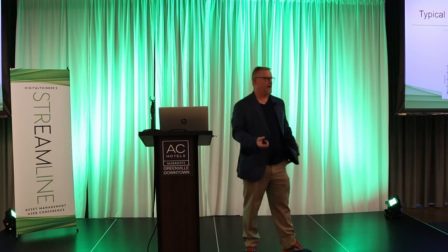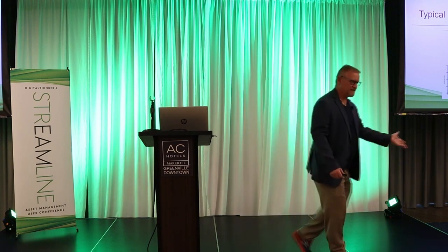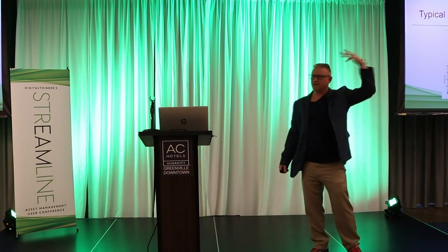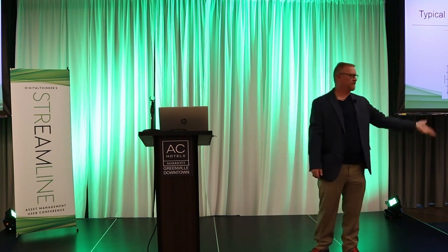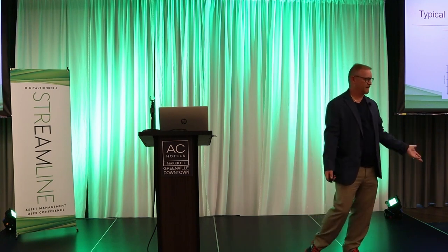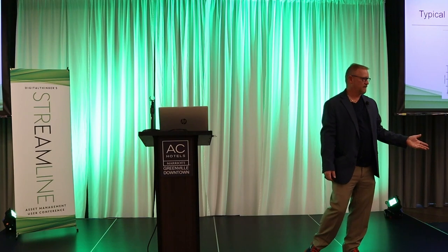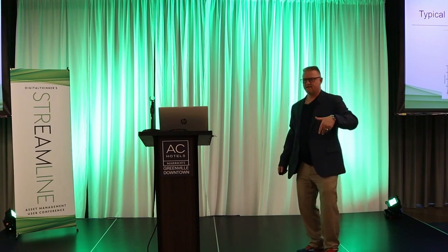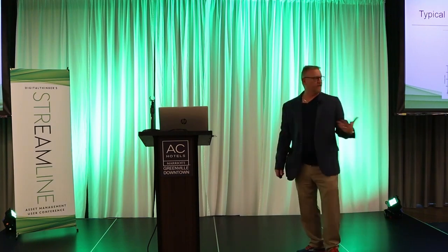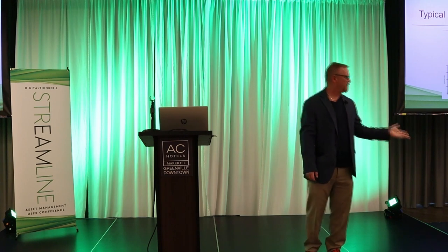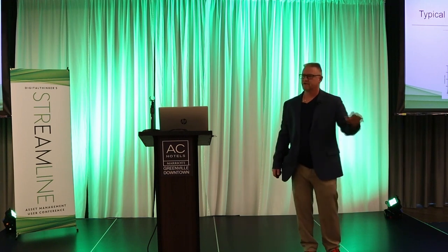For example, a belt frequency is less than turning speed. So if I have a high peak at below 1 times turning speed, there's a really good chance I have a belt issue. If I have high 1 times, 2 times, 3 times, 4 times in a row, that's a really high probability I have mechanical looseness.